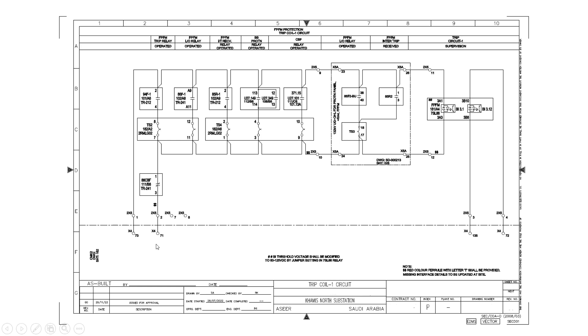But in some cases the circuit breaker does not operate due to a failure. For example, 86F1 — the lockout relay — operates and gives a tripping signal, but due to a mechanical problem the circuit breaker does not operate. In this case, the positive will continuously extend to the trip coil because the breaker's NO contact is still closed. The trip coils are high-burden coils; they draw more current when energized, and continuous energization will damage the trip coil due to excessive current and heat.